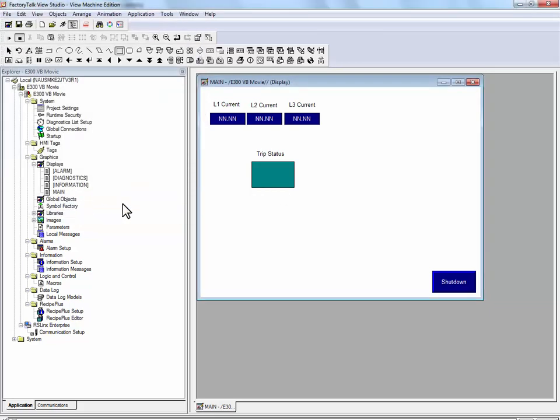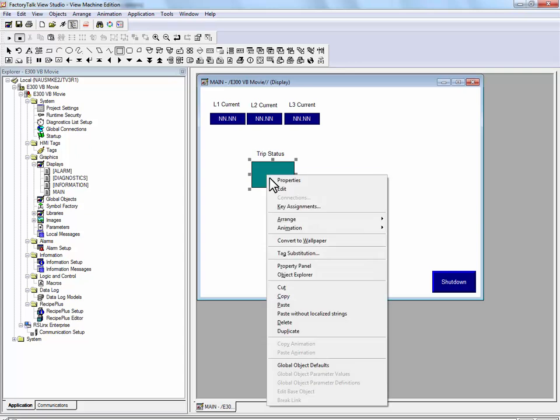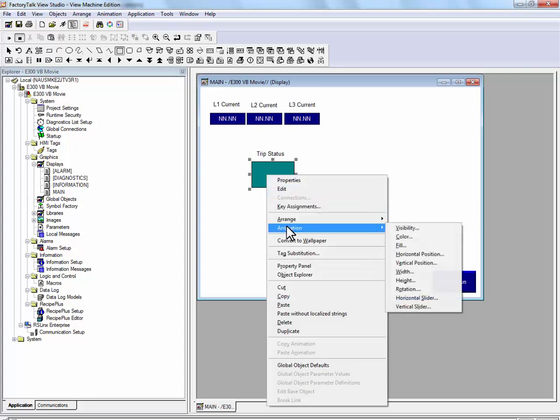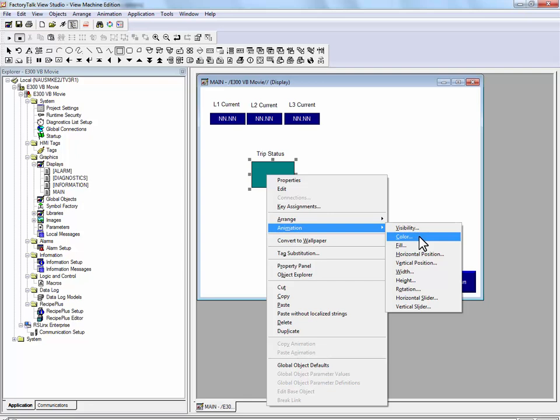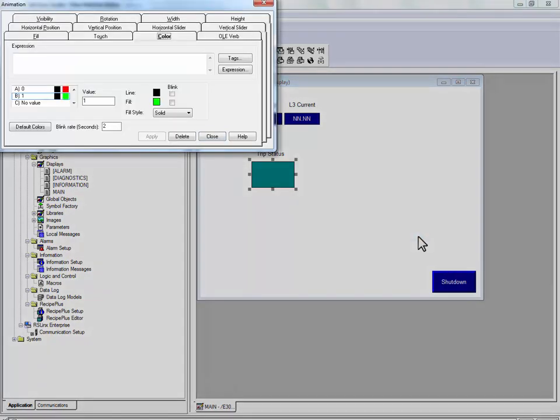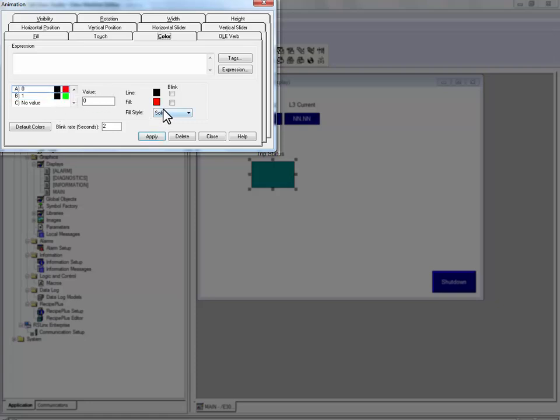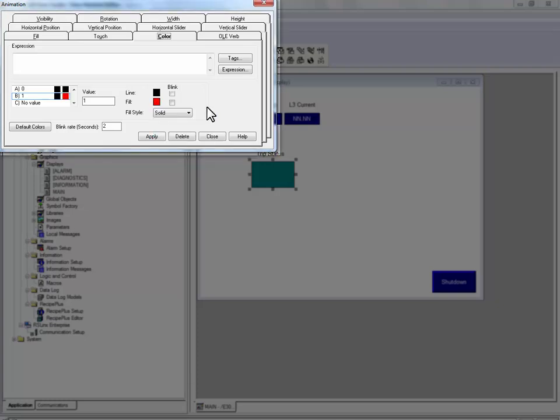For this rectangle, we will use the animation properties, specifically the color animation. When the trip present bit is set at 0, the rectangle will be solid black. When the trip present bit is set to 1, we will make it a blinking red graphic. It will blink between red and black.